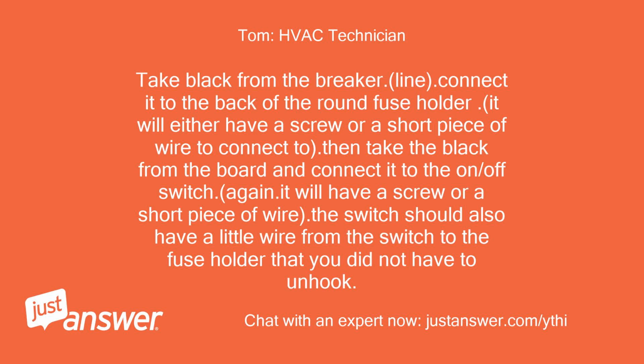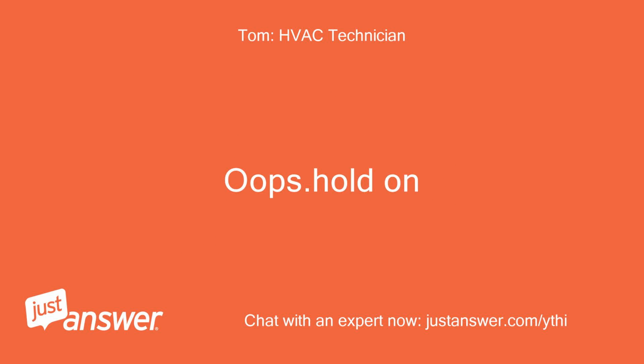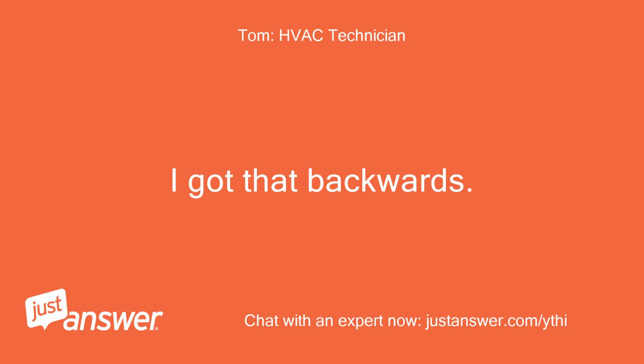Take black from the breaker line. Connect it to the back of the round fuse holder. It will either have a screw or a short piece of wire to connect to. Then take the black from the board and connect it to the on/off switch. Again, it will have a screw or a short piece of wire. The switch should also have a little wire from the switch to the fuse holder that you did not have to unhook. Oops. Hold on. I got that backwards. Let me retype it, please.